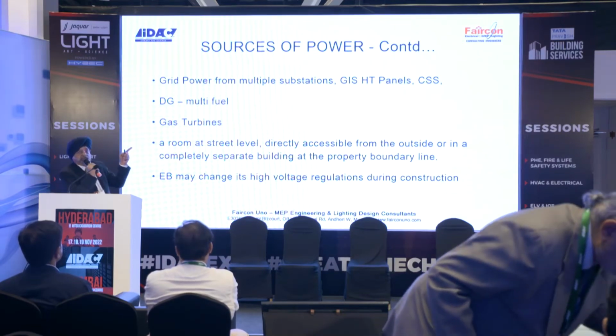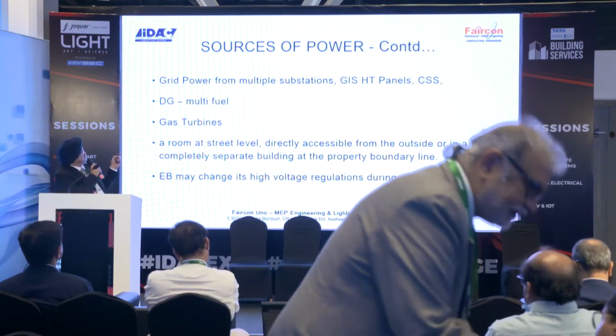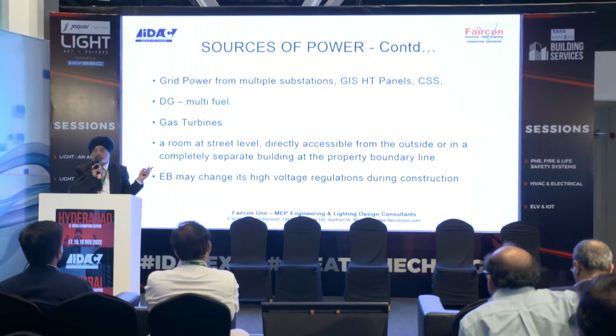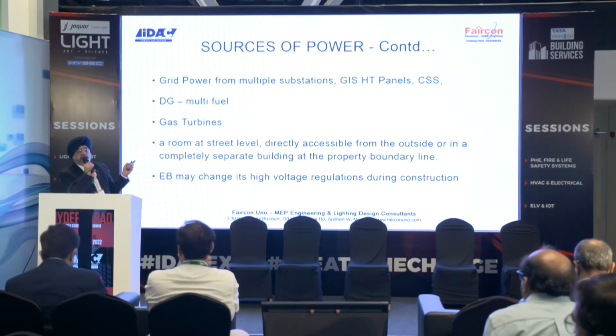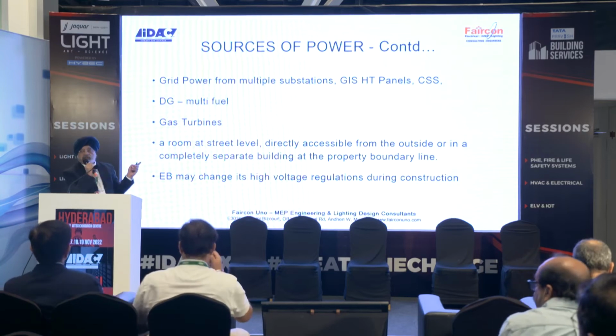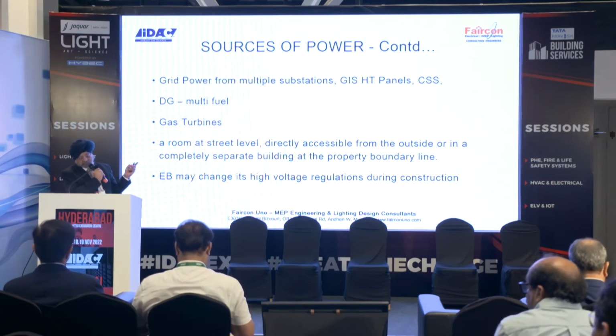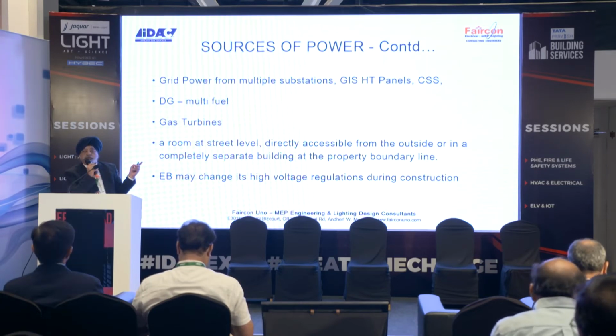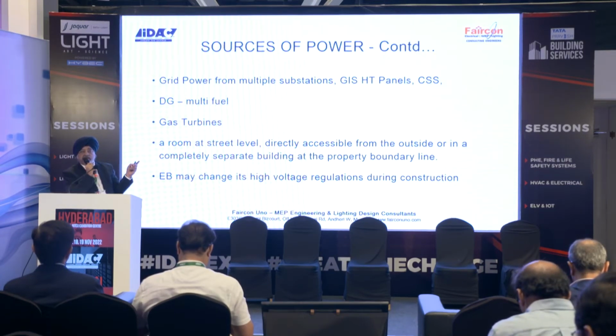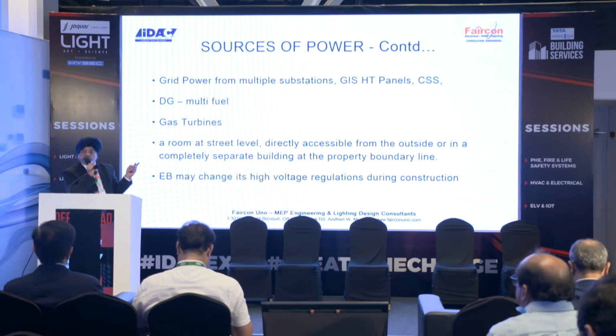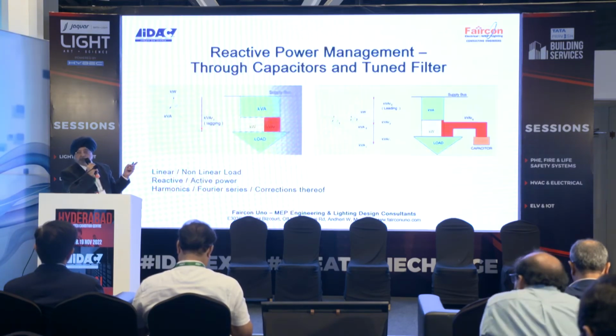See, gas insulated HT panels and compact substations are basically to reduce the footprint size of the equipment. DG multi-fuel, this is important. Diesel is not going to be easily available in future. So we will depend on other fossil gases like CNG, PNG, LPG, propane also. Propane is a very good option. Only catch is it is not conducive for engines, and it has a lot of knocking and vibration. But Caterpillar is able to give you 1 megawatt engines using propane. We have used it successfully.